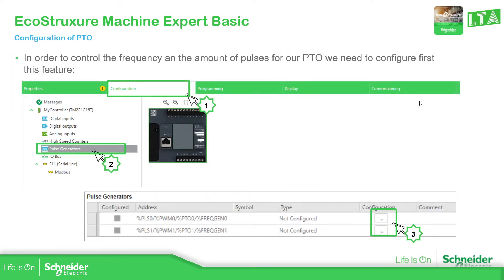To configure the PTOs, we just need to go to the configuration tab at the top. Then it depends on the controller that you have, because if you want to use the PTO, it's important that we have transistor output. Otherwise it's not going to work, and this option is not going to be enabled.